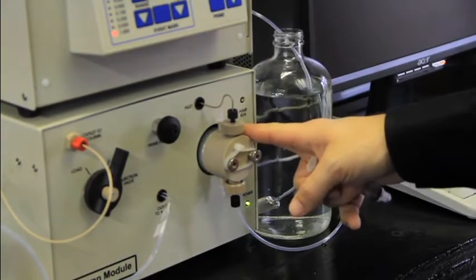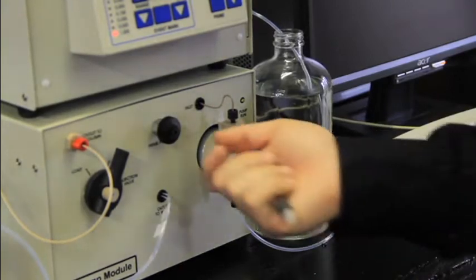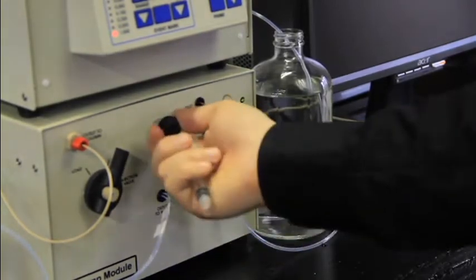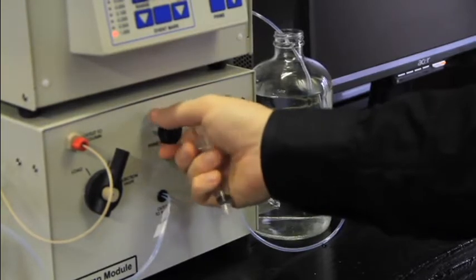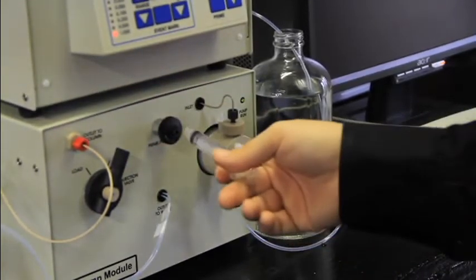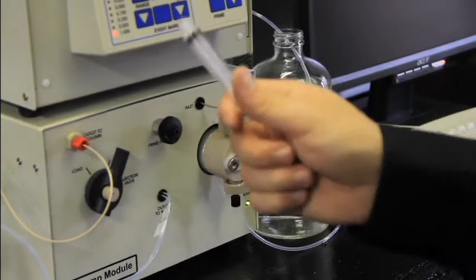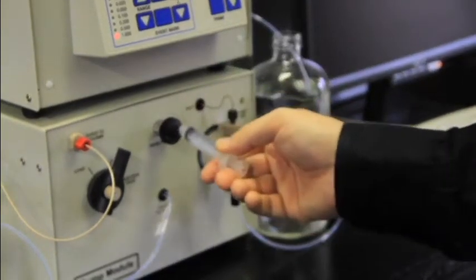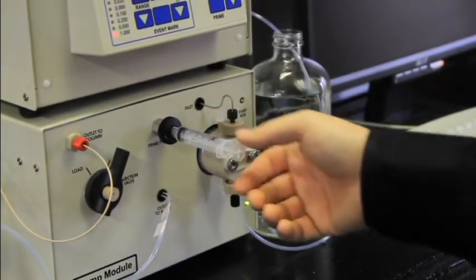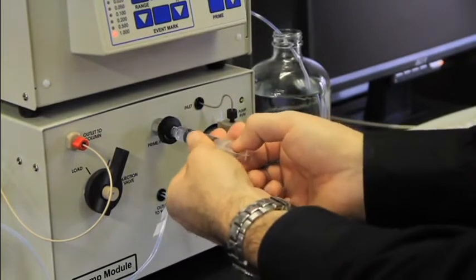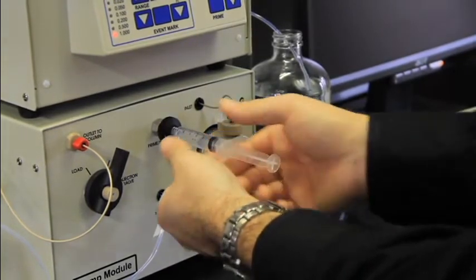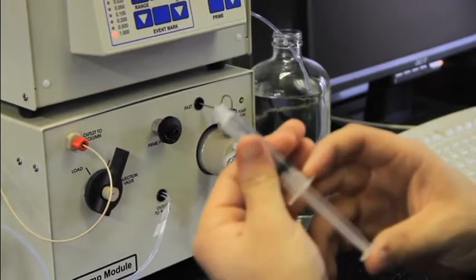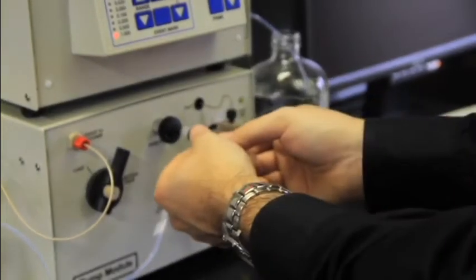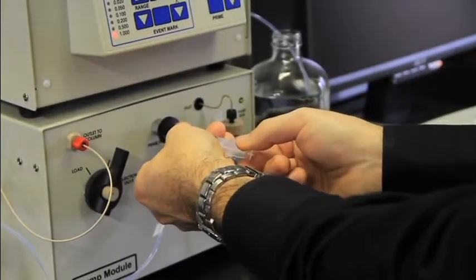before running the system. To do this, what we'll do is open the prime purge valve here a few turns to the left, and then place a Luer lock syringe, several are included in your packing kit, on the prime purge valve and pull backwards. Now, in this case, we've only drawn air, and you may need to repeat this several times to actually get the solvent to start coming out.